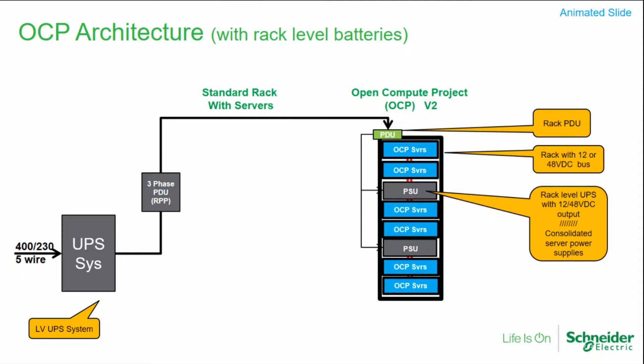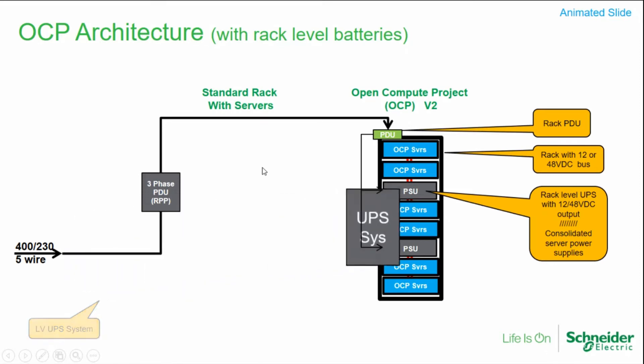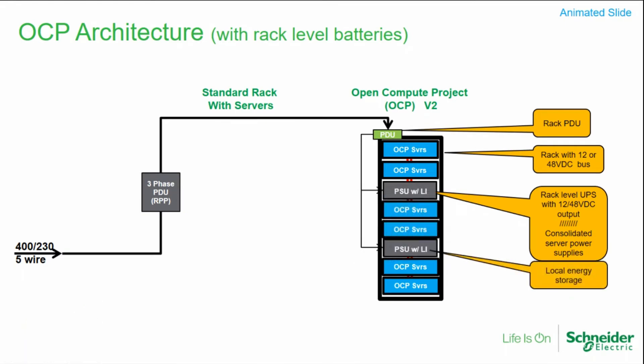You can configure these for N+1, which is pretty typical with open compute, and you can still have two inputs to the overall PSU — there are other configurations as well. Another interesting thing when the spec was published: because of the advent of lithium-ion batteries, which are smaller, lighter, and pack more power in a smaller space, if you couple those power supplies with batteries you can put the UPS function right there in the rack — specified for maybe 90 seconds or three minutes of runtime.